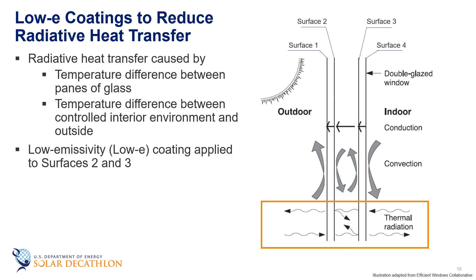Now we've discussed strategies for reducing conduction and convection — how about radiation? With radiative heat transfer, we have a temperature difference between the two panes of glass, as well as between our controlled interior environment and outside. To lower radiative heat transfer, we add a thin, nearly transparent coating called a low emissivity or low-E coating to the glass surfaces. Typically this coating is silver or tin oxide. Because the coating is somewhat fragile, it's often placed on the inner layers — surface 2 or surface 3, and sometimes both — lowering the U-factor of the glass.